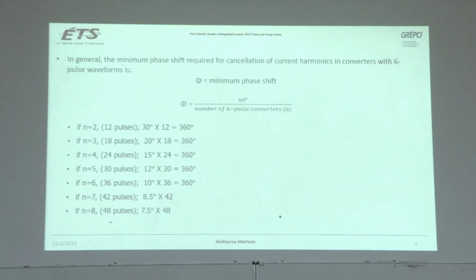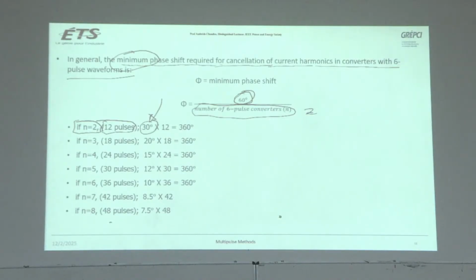In general, in DD0 and DY1, we saw a 30-degree phase shift, which is helping in cancelling the harmonics. In general, the minimum phase shift required for cancellation of current harmonics in converters with 6-pulse waveform is 60 degrees divided by the number of 6-pulse converters. For example, in our DY1 and DD0, we used 2 6-pulse converters, which gives you 12 pulses, 6 multiplied by 2. So 60 divided by 2 means you need a 30-degree phase shift, and this is what we gave.